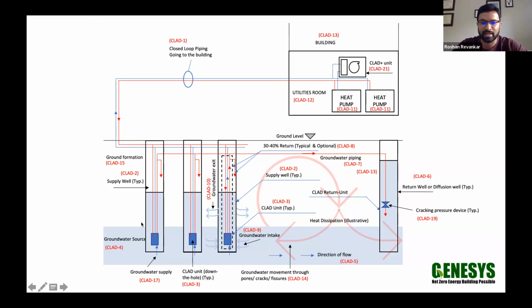The way we design location of supply and discharge wells is very similar to how you would do in an open loop system, where you pick up the supply and discharge it in the direction of flow of groundwater. And a lot of this information is available online on the direction of flow in general. So pick up water and drop it into a discharge well. Again, it does not have to be discharged into a well. It could go into a surface water or stormwater sewer and so on. Or what we are seeing in a few applications is it's also used for domestic water use if it's permitted there.